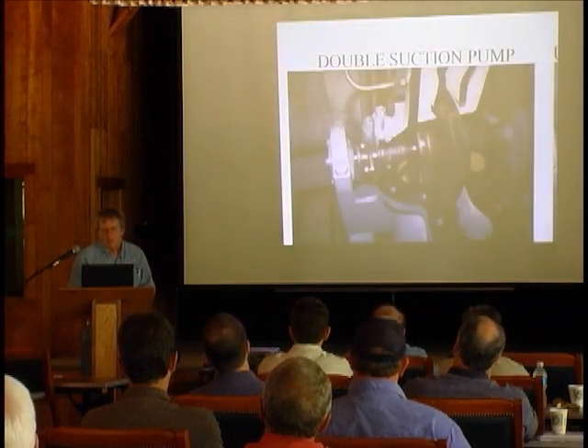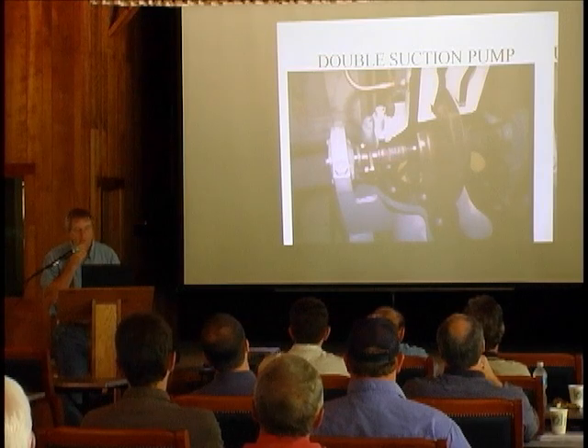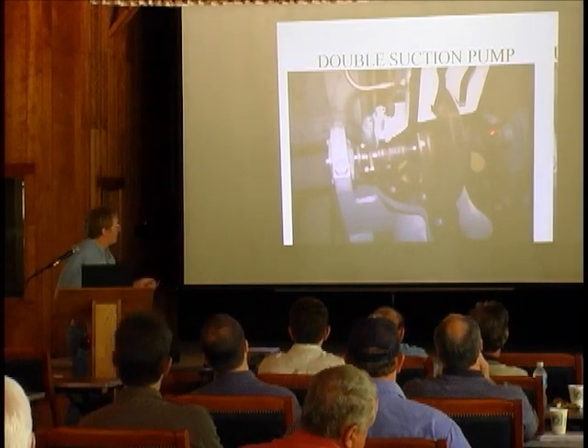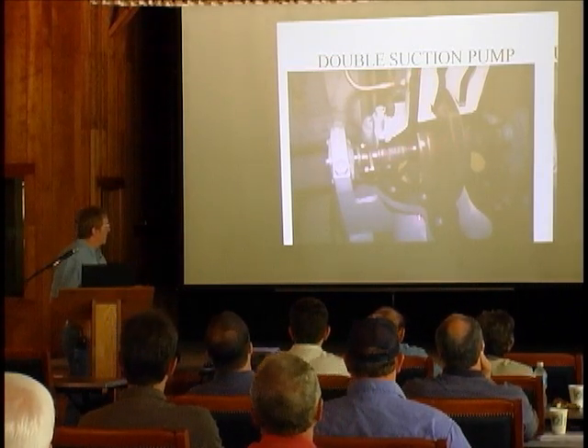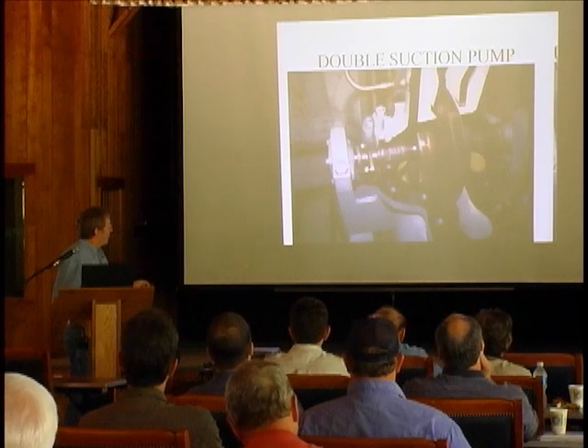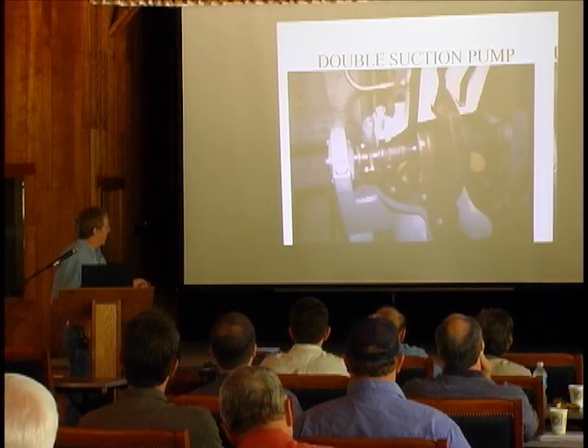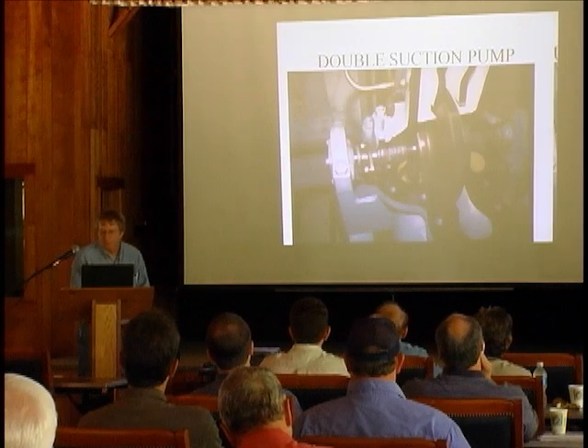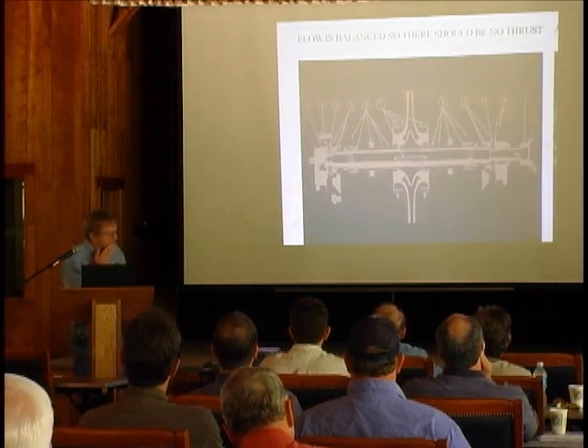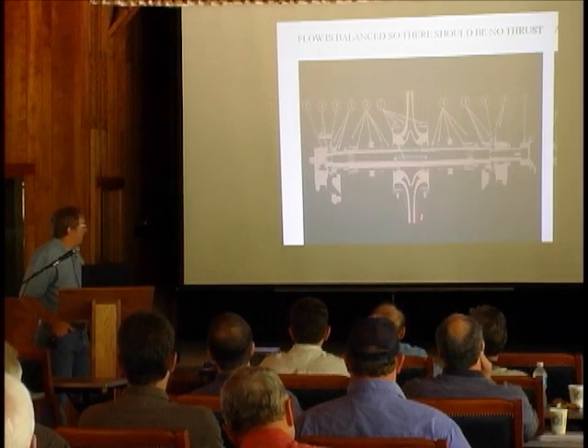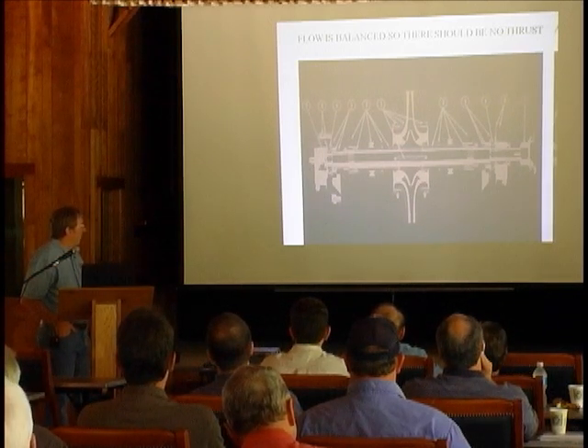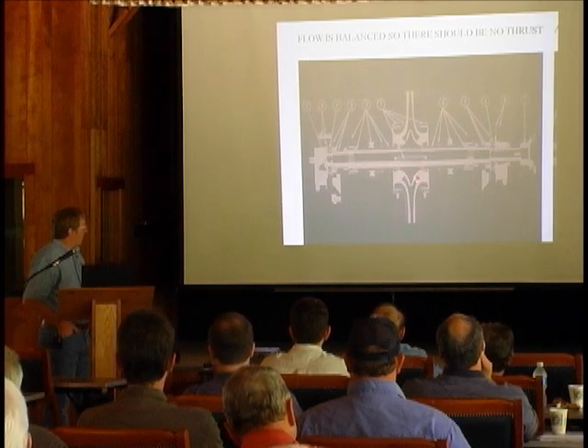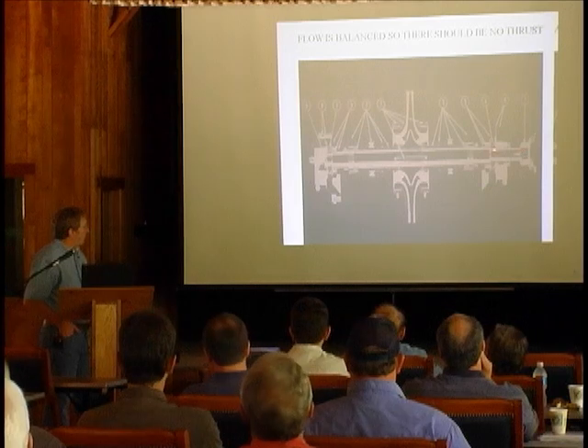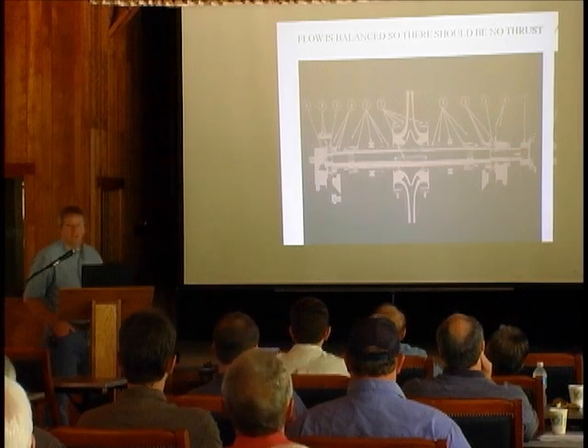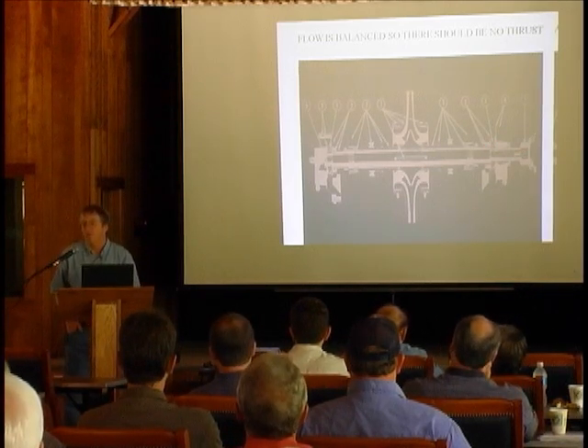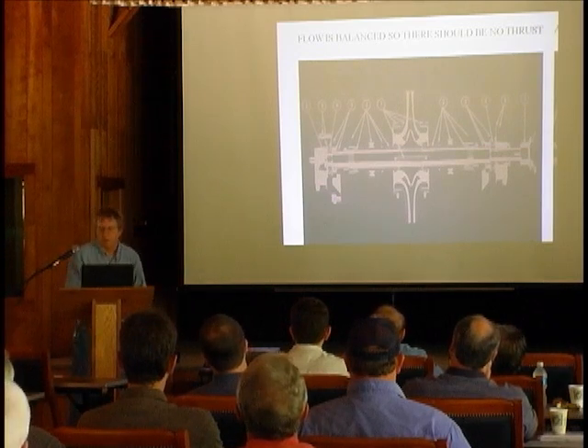Okay. So the next one was sort of the opposite situation. It was a double suction pump, like this. This is sort of a cutout where the fluid flows in here and it flows out the impeller, and then you've got your seals and your bearings here. In a double suction pump like this, it really should be thrust neutral. In other words, we have flow coming here and here, and everything should be flow neutral. So you have bearings here, and they're not really designed to take a thrust load. They're just designed to take a radial load.